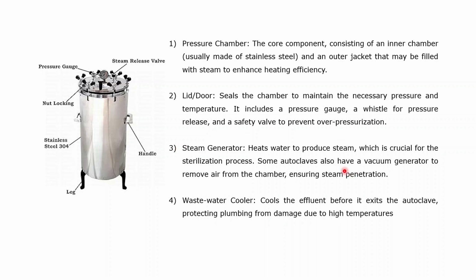What sterilization process takes place in that case? Wet sterilization. And also, as it is at a high pressure, it promotes that sterilization environment. And apart from that, there is a wastewater cooler there. So if water has to be removed from the autoclave directly, then it cools down the water so that whenever the water moves through the pipes present in the autoclave, it won't hamper those pipes.